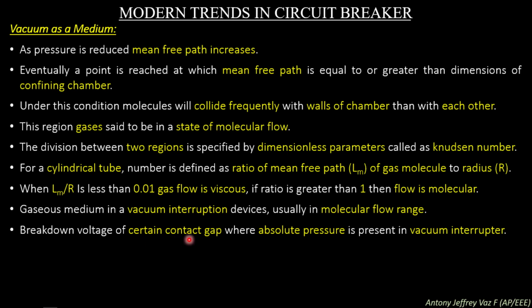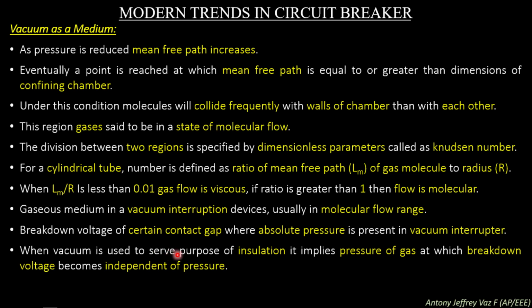Consider the breakdown voltage of certain contact gaps where absolute pressure is present in vacuum interrupters. When vacuum is used to serve the purpose of insulation, it implies the pressure of gas at which breakdown voltage becomes independent of pressure. For insulation with oil or air as the medium, the breakdown voltage depends on the pressure of the medium which is present. But in vacuum, the contacts are placed so that there is no medium between them. So the contacts will not have any medium to be connected between them.